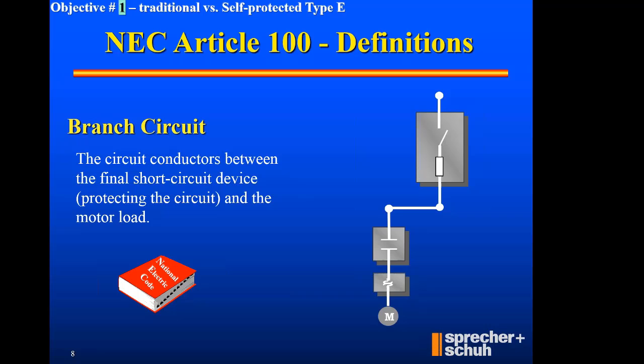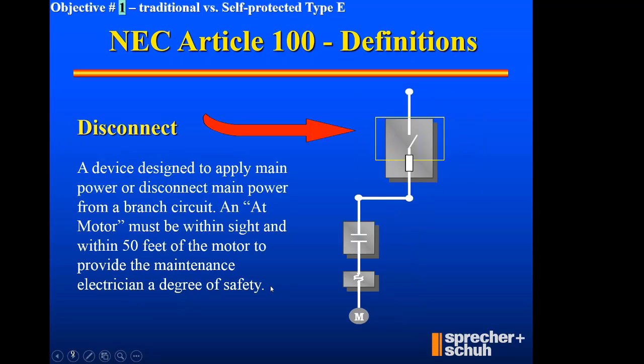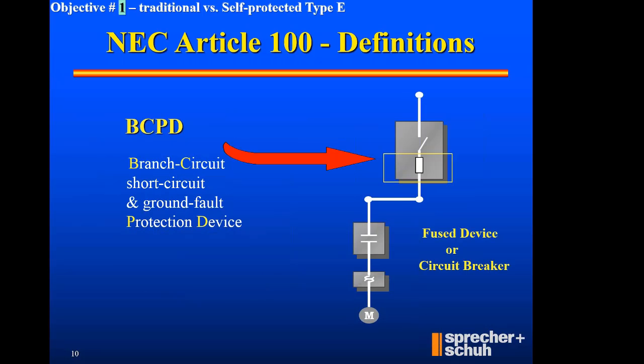So, okay, a real quick brush on background information, just so that everyone understands from a National Electrical Code perspective that a branch circuit is the circuit conductors between the final short circuit device and the motor load. So this is the circuit that we're showing on the screen. So identifying all that, breaking down all that individually. Okay, I've got the disconnect portion squared, and the disconnect is, hey, I have the ability to apply power or take a power away. From an at motor perspective, I need to be within 50 feet and within sight is what National Electric Code says. So if I'm a branch circuit, hey, I've got to have means of disconnect. So I've got to be able to turn it on and off.